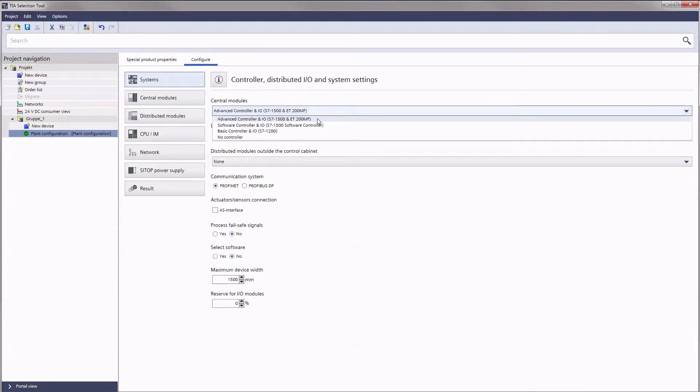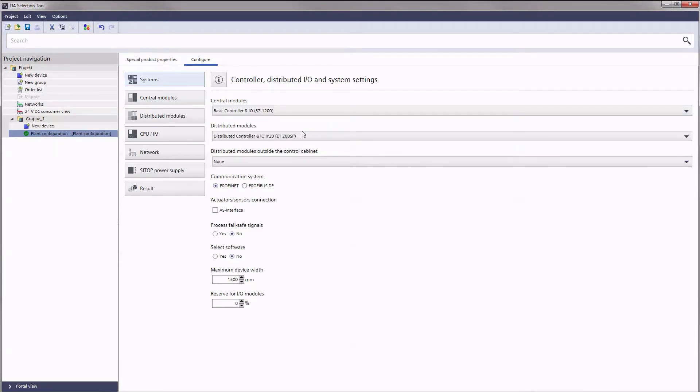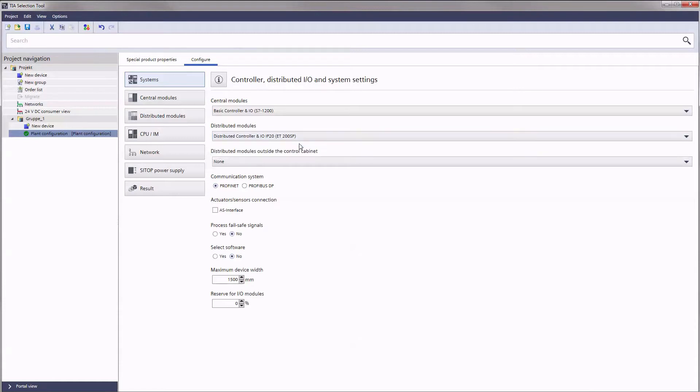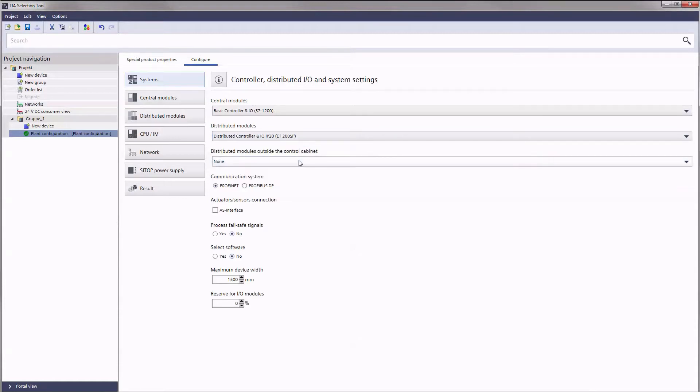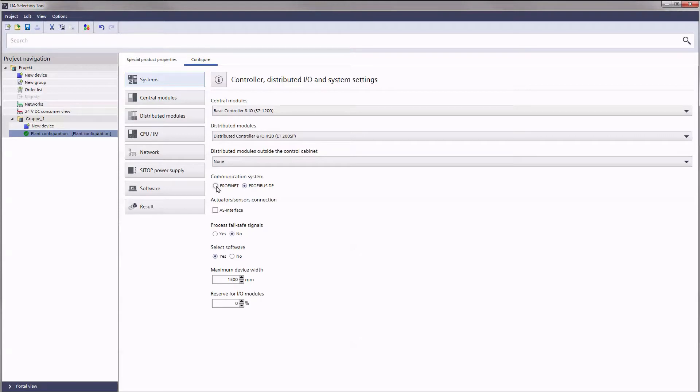We begin our project with a SIMATIC S7-1200 basic controller and the ET-200SP as decentralized IO system in the cabinet. We decide on software and select PROFINET as a bus system. You also indicate here whether failsafe signals are to be processed or not.